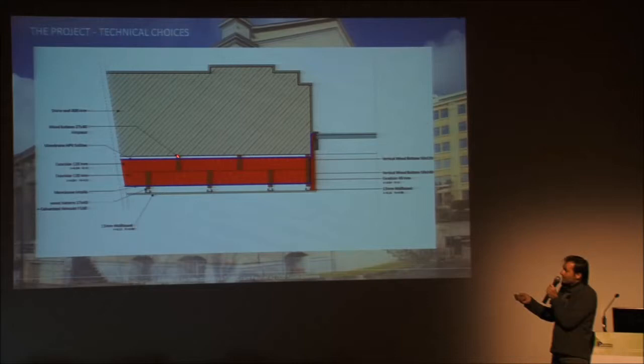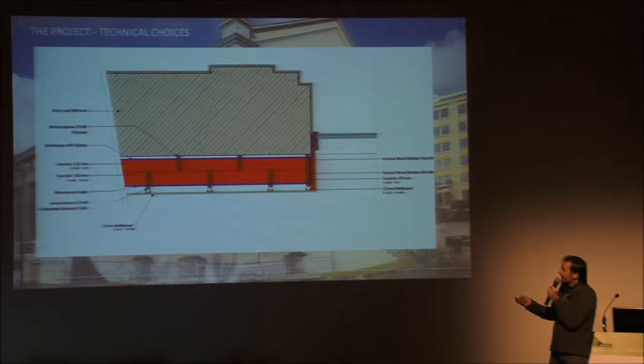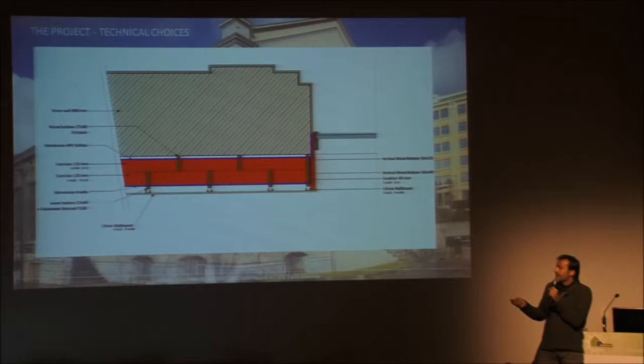Here, there's an airtightness membrane, which is called Intello, and here there is another one, which is called Solitex. When you put internal insulation, it's very dangerous because you can have moisture problems and humidity and condensation right here because the outside world is very cold. So we checked that with WUFI, and the problem was really important, and the problem was real here.